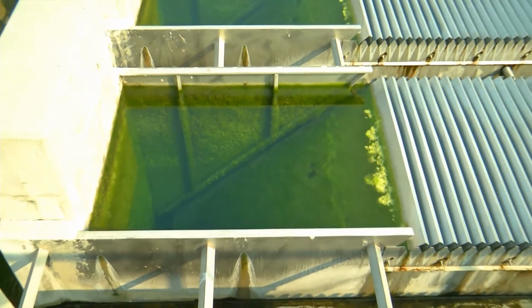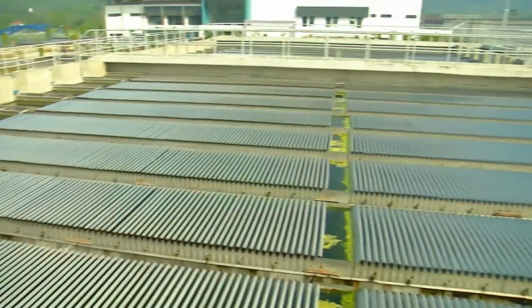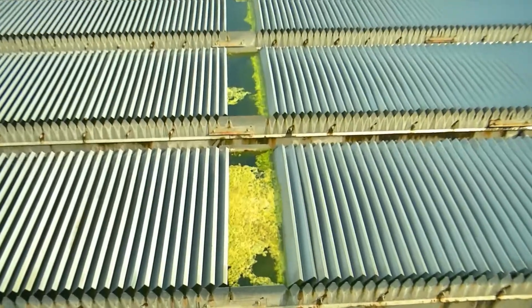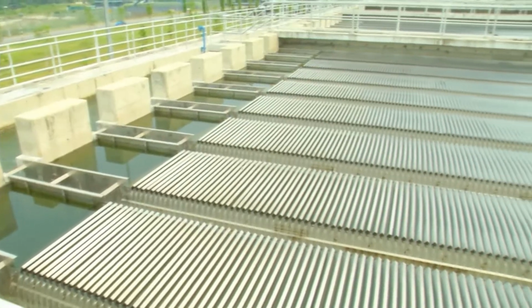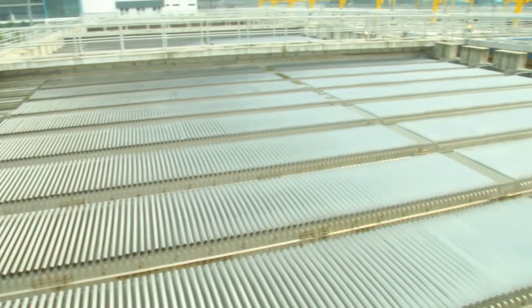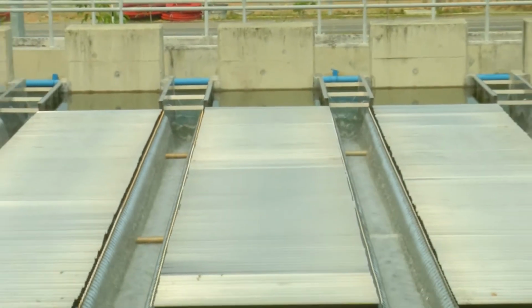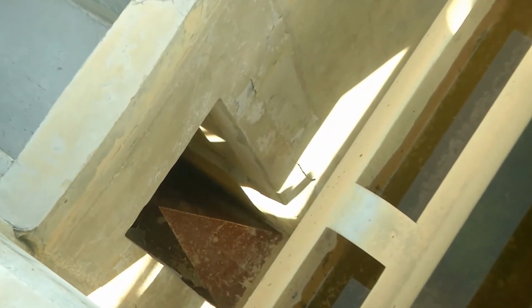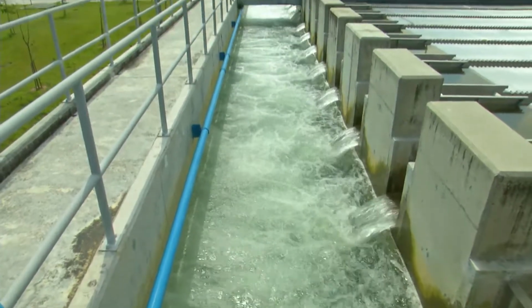Clarification process involves separation of solids generated from the flocculation process from the water. The lamellar clarifier system operates according to the countercurrent or upflow principle. Water enters and exits the system through channels, which are divided into 2 sections consisting of the lower section for incoming water and the upper section for discharge of clarified water.